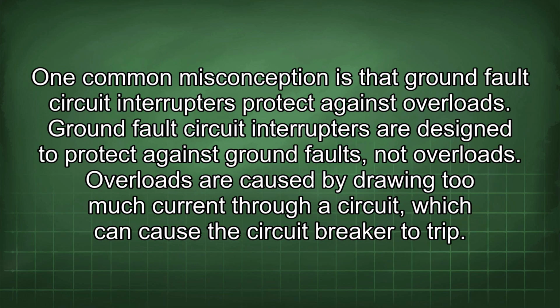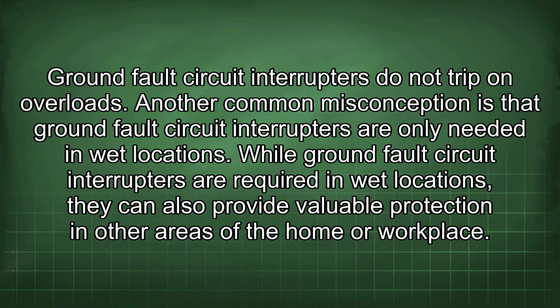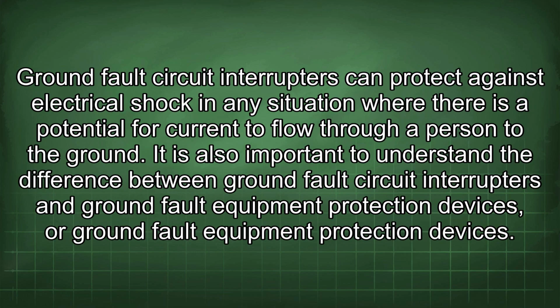One common misconception is that ground fault circuit interrupters protect against overloads. Ground fault circuit interrupters are designed to protect against ground faults, not overloads. Overloads are caused by drawing too much current through a circuit, which can cause the circuit breaker to trip. Ground fault circuit interrupters do not trip on overloads. Another common misconception is that ground fault circuit interrupters are only needed in wet locations. While ground fault circuit interrupters are required in wet locations, they can also provide valuable protection in other areas of the home or workplace. Ground fault circuit interrupters can protect against electrical shock in any situation where there is a potential for current to flow through a person to the ground.